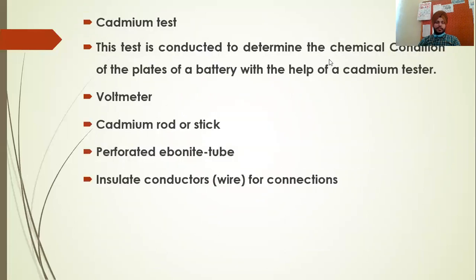The next test is the cadmium test. The cadmium test checks the chemical condition of the plates of the battery. Cadmium is a metal used for this test. The cadmium tester has four main parts: a voltmeter, a cadmium rod or stick, a perforated ebonite tube, and an insulated conductor wire for connection.